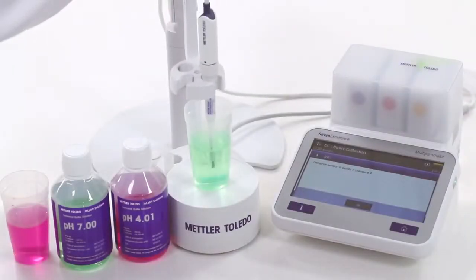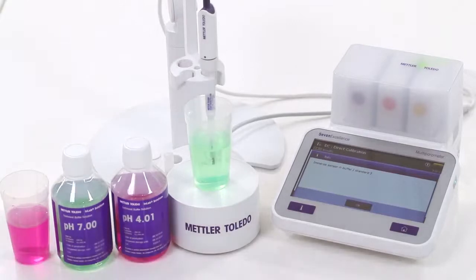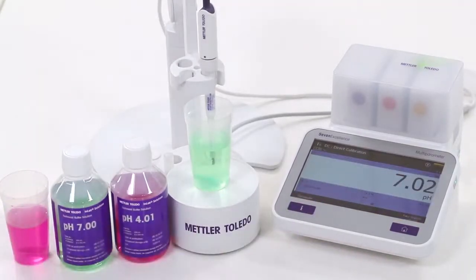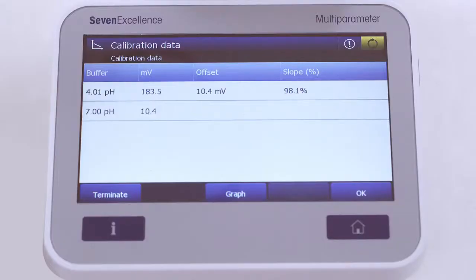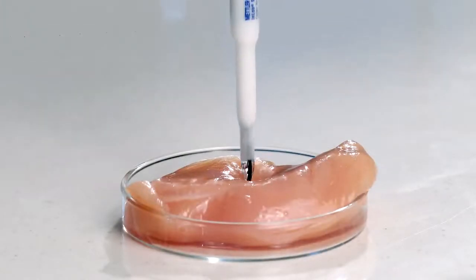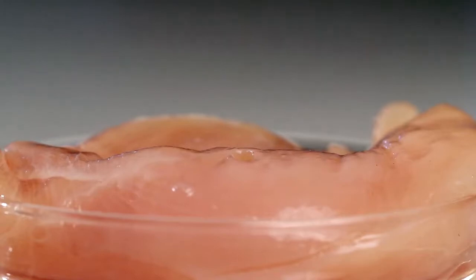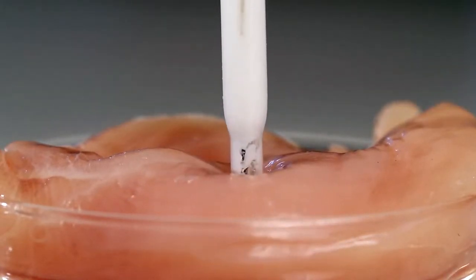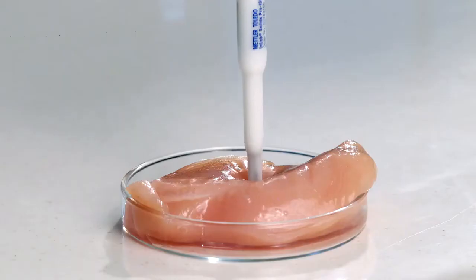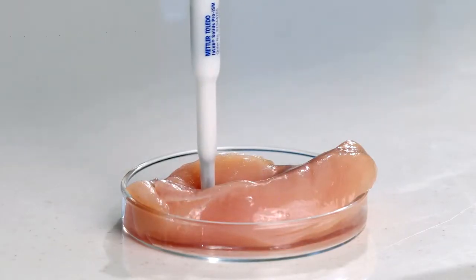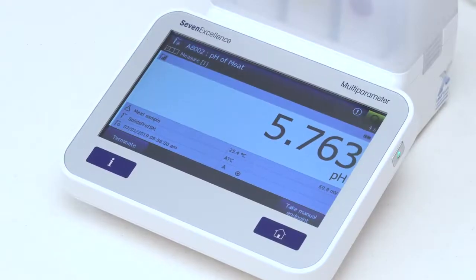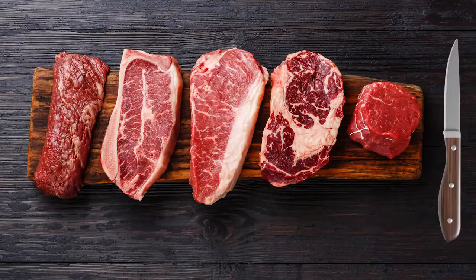Calibrate the electrode with pH buffer solutions from Mettler Toledo. Use the buffers to bracket the sample pH range. Measure the pH by gently piercing the electrode into the piece of meat sample. Make sure that the open junction is completely immersed into the sample. Repeat the measurement at various positions to obtain a representative pH reading. Alternatively, a slit can be made to ease the electrode insertion into the sample mass.